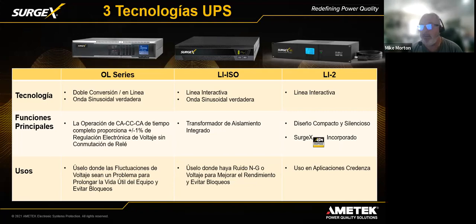The only difference between this and the products you're seeing in your market space is that this particular device, the LI-ISO series, is equipped with isolation transformers built in. So they give you neutral to ground control, plus power conditioning and surge protection. These devices are very important for those particular applications.